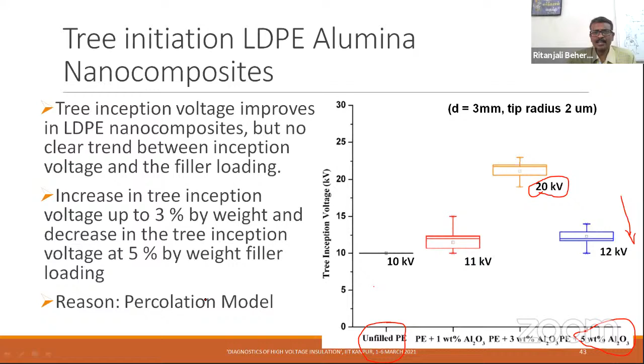So the inception voltage is increased slightly. When it is 3 weight percentage, then the inception voltage becomes 20 kV. Appreciably increased the tree inception voltage. And when it becomes 5 weight percentage, it suddenly dropped down to 12 kV. So this tree inception, though it improves significantly from 10 to 11 to 20 when the filler concentration is increased up to 3%, drops down to 12 kV when it is increased to 5%. The reason actually could be due to the percolation.